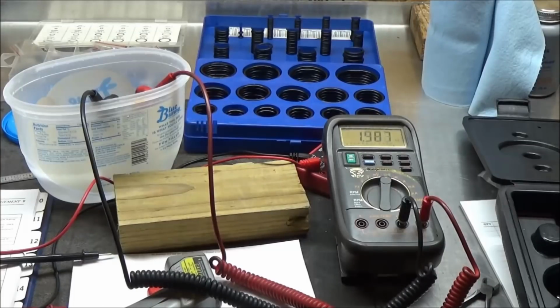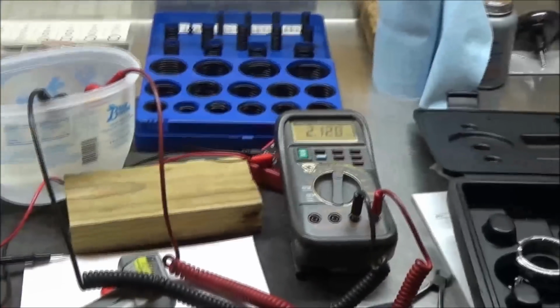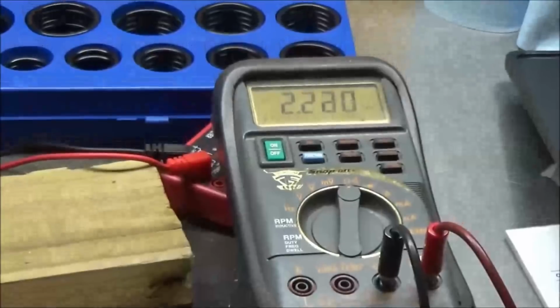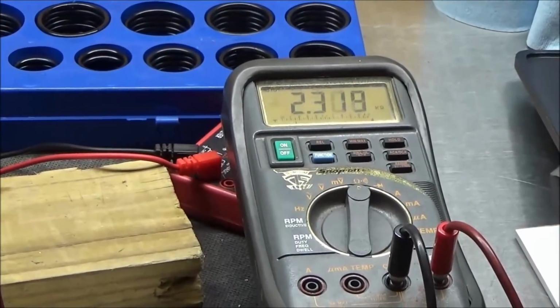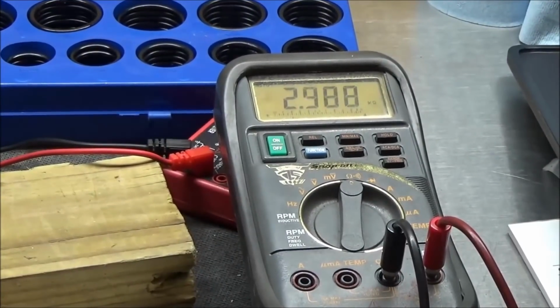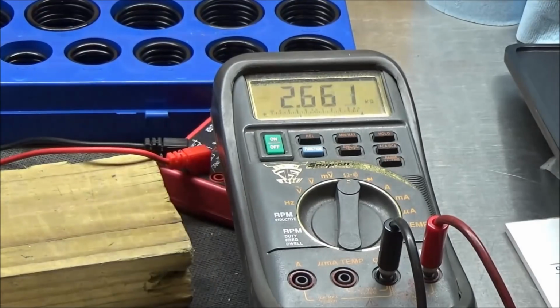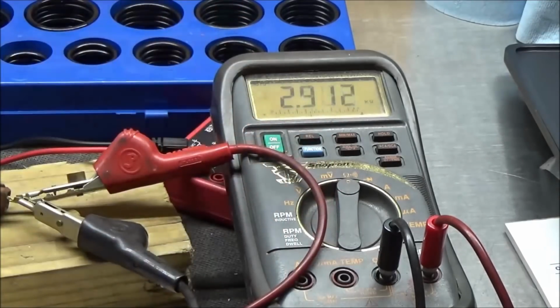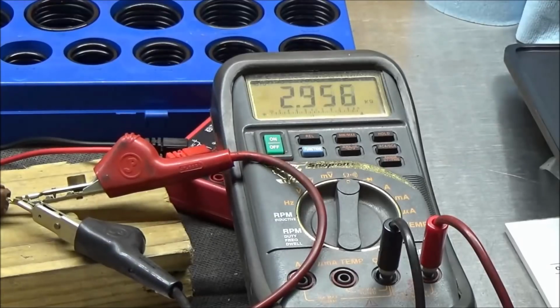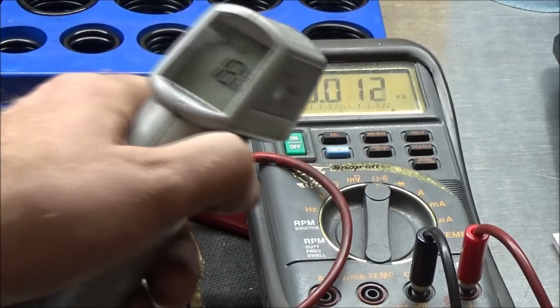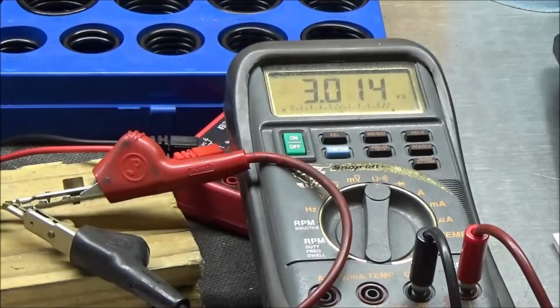Now what you're going to notice - look at that. What's happening is that sensor is just immersed in there, and you can see the resistance number going up. I'll pull that back out now - should have some stability here. I'm at 3,000 ohms, and that is right on track with what the service manual says.